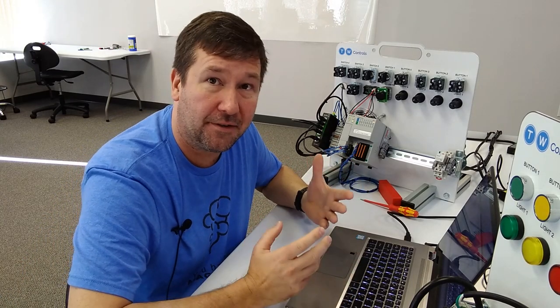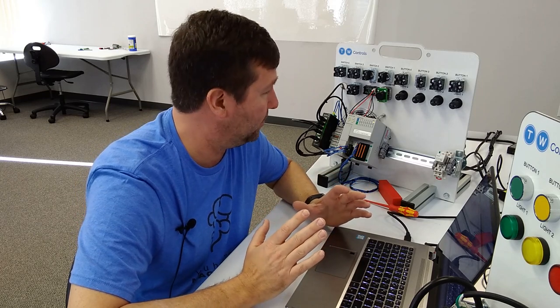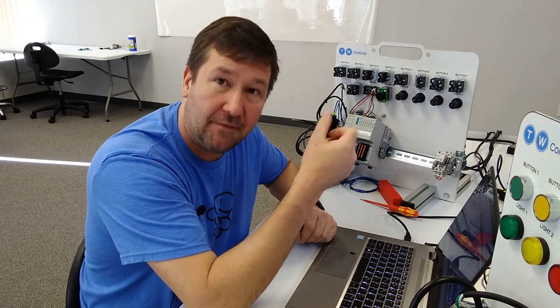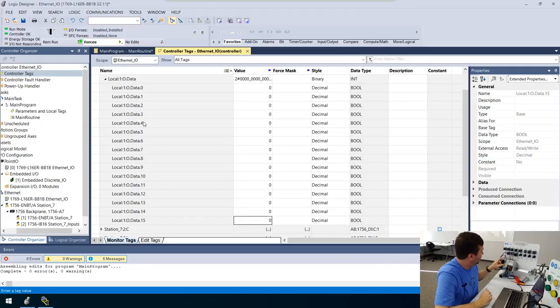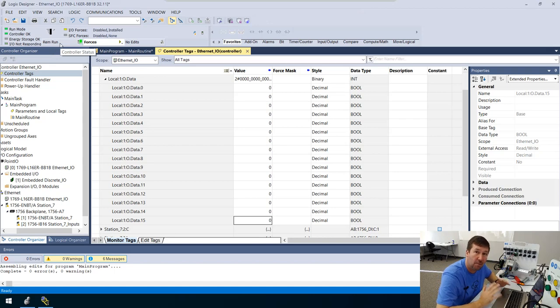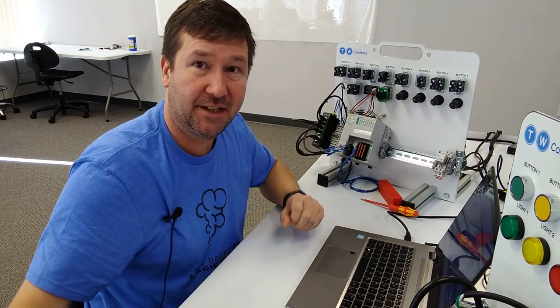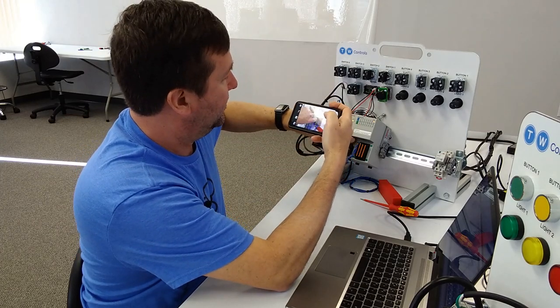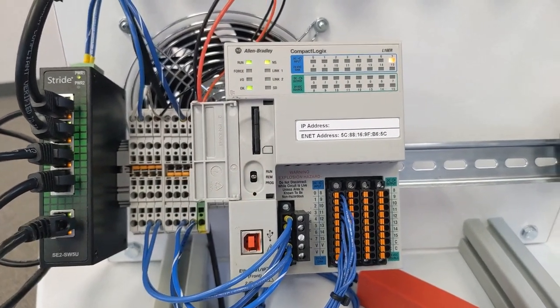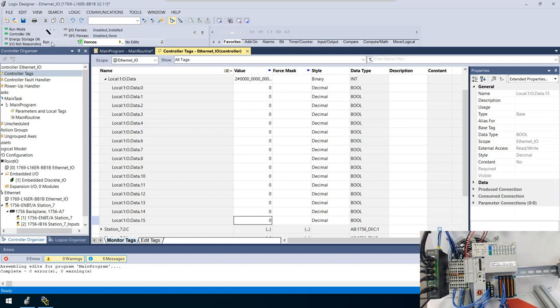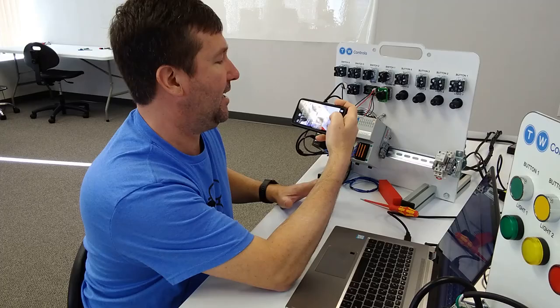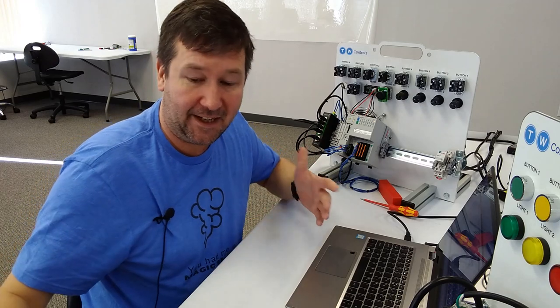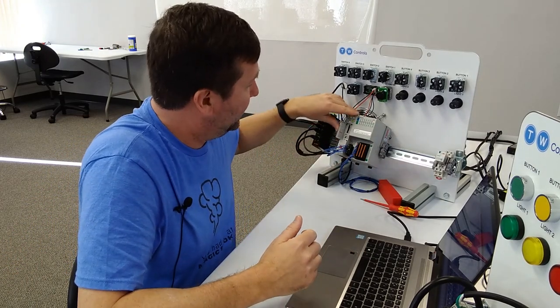But let's say that either there are no spare outputs or we just are not comfortable with that. There are a few other things that we can do. And here's where I kind of butt heads with some of the cyber security people who are insisting that we put the processor in run mode. And if it has a key, we remove it. As I believe this is a very important safety feature is that right now in Studio 5000, I can see I'm in remote run. Well, the only difference between remote run and run is the key switch position. Now on the CompactLogix, it doesn't actually have a key switch. It has a selector switch here. But if I watch this remote run here, when I select run, you're going to see that it changes to run mode. And if I go back to remote, it goes back to remote, it did not affect the machine's operation. But it did give us an indicator. But again, okay, maybe the key switch isn't there. Maybe the control panel is locked. So you can't get into it.